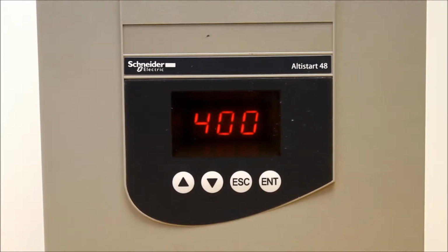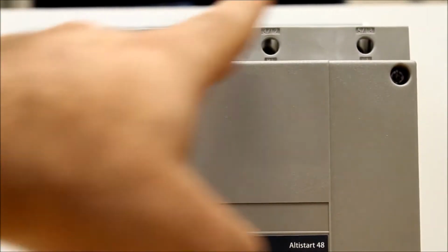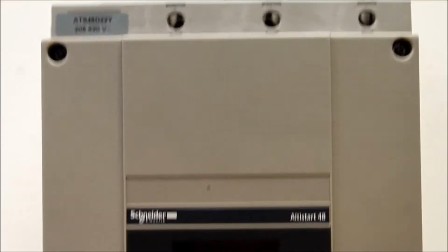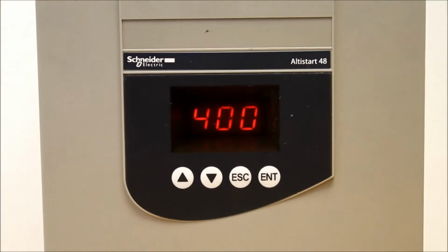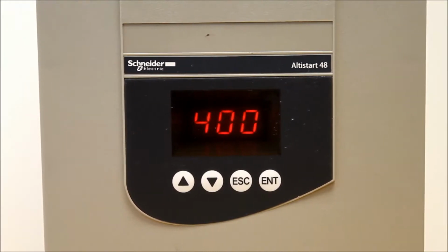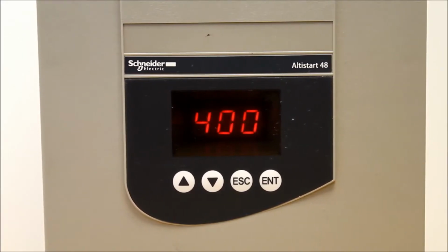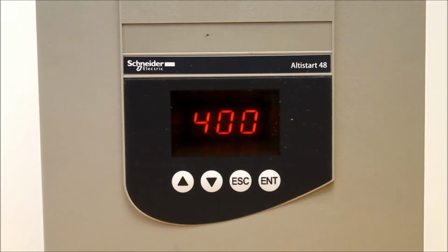So there might be other problems. There might be a problem with your line power, where you can measure L1, 2, and 3 and make sure those are not dropping too low, because the lower the voltage potential, the higher the current draw. You might have a motor issue. You might have imbalanced current draw by the load. You might want to check the current at each phase coming out of the motor while it's ramping up. Or you may have a motor problem, maybe the windings are the issue. It might be a very long distance run. The load may be overloaded. The motor may be undersized. There are a number of things that may be going on.